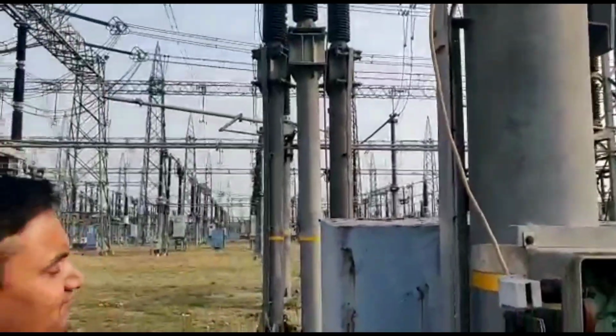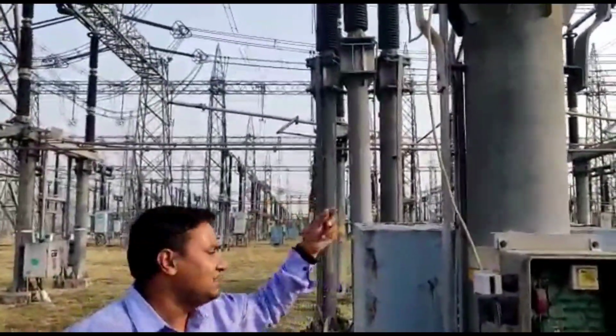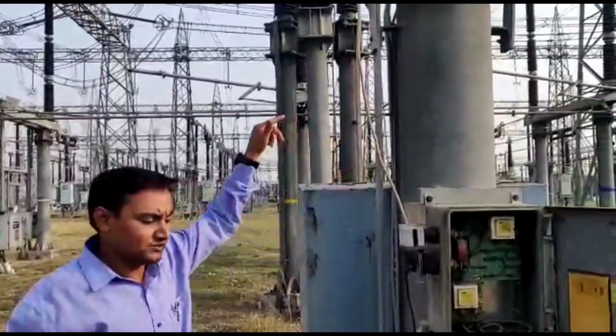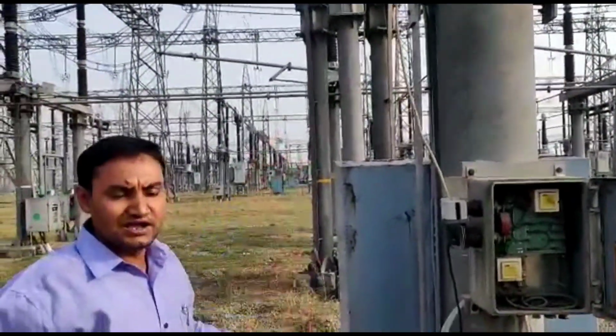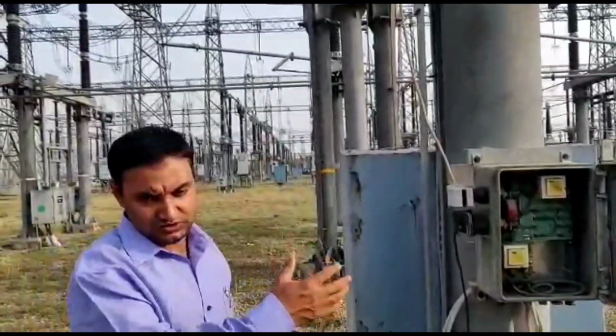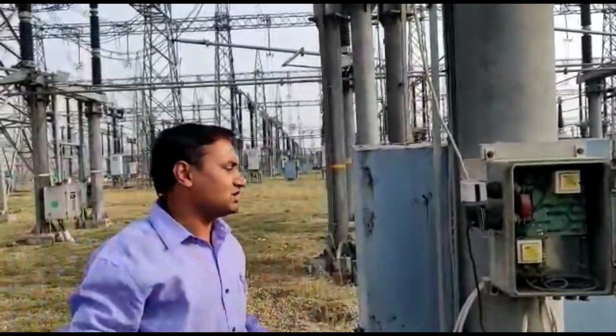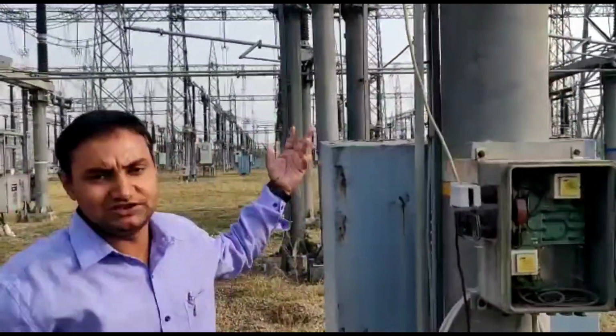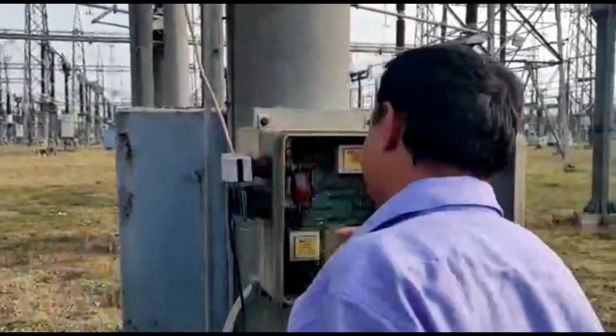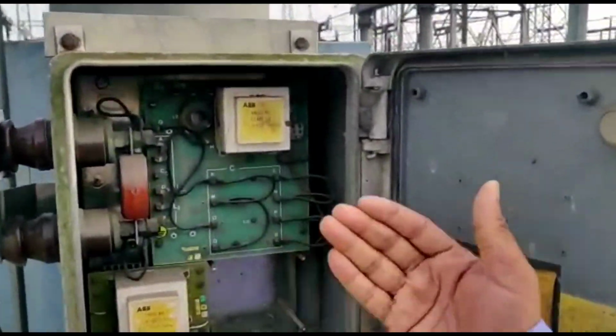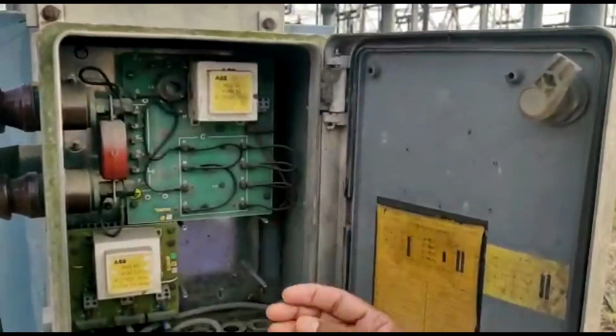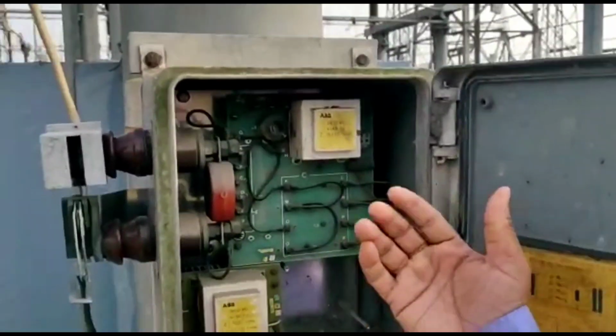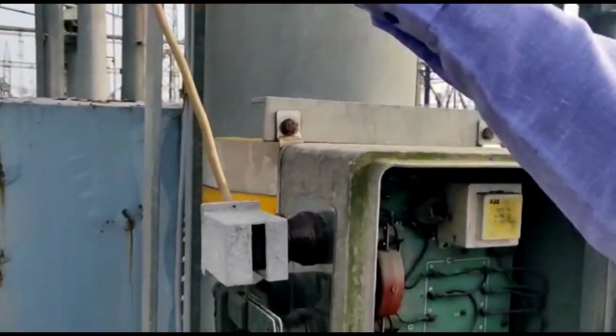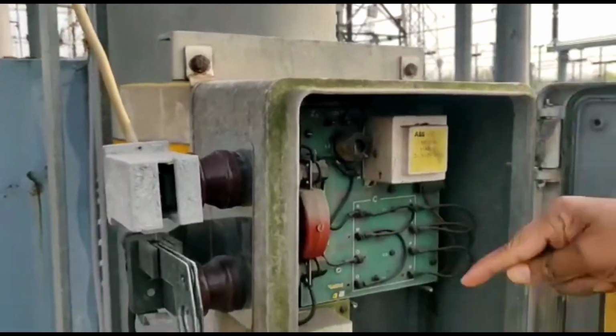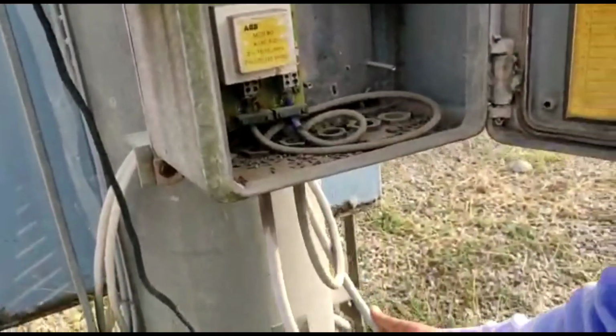But then there is a chance that if there is any over voltage in this line, and you are using this wire directly from the high frequency terminal to your PLCC equipment, that over voltage on the transmission line might damage your PLCC equipment. So what we are using is an additional equipment called line matching unit or LMU.